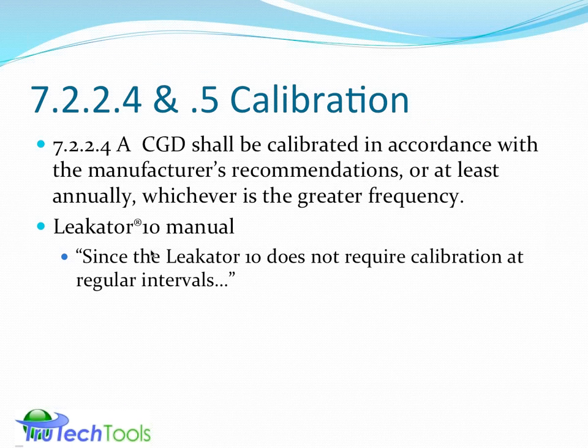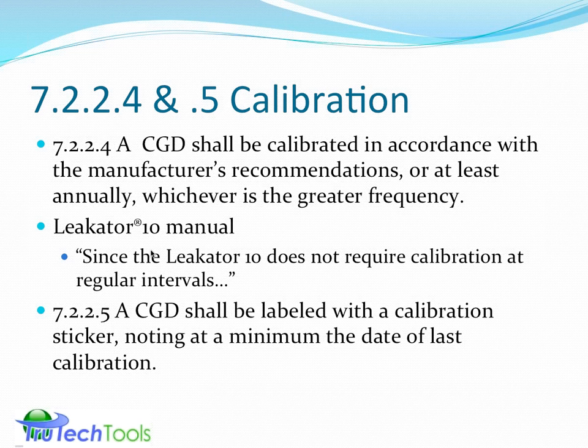I have a little difficulty with this because the Leakator 10 manual, the manufacturer says, does not require calibration at regular intervals, which sort of makes a point of confusion here. How can you calibrate it if the manufacturer says it does not require calibration? This is one of the spots that we believe BPI is going to get corrected very shortly with the next release of the standard. Also, the detector should be labeled with a calibration sticker noting the last date of calibration. So that's a pretty simple, straightforward requirement there.